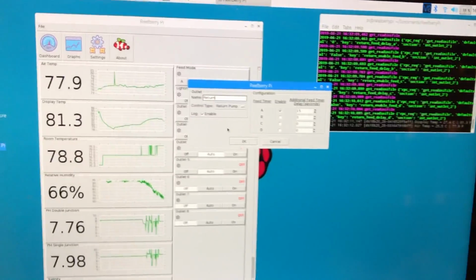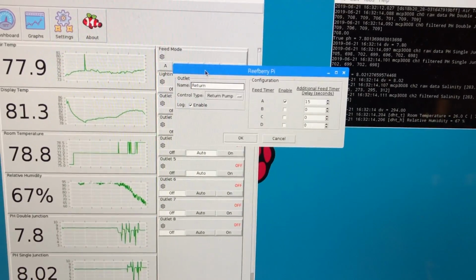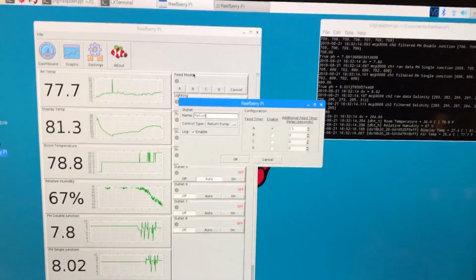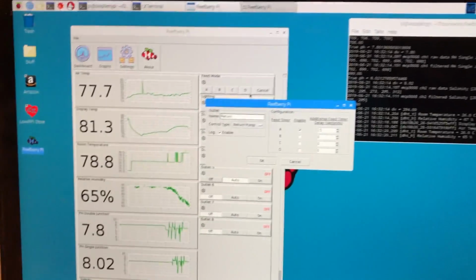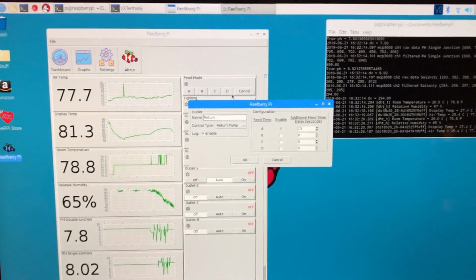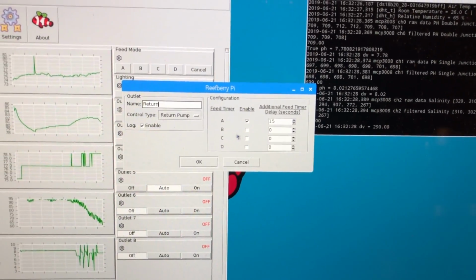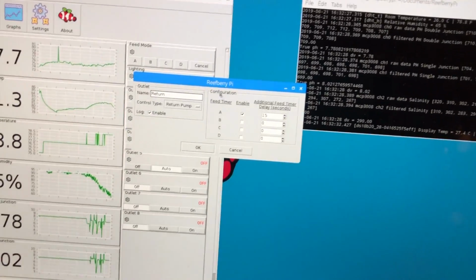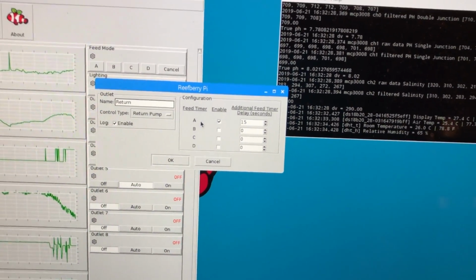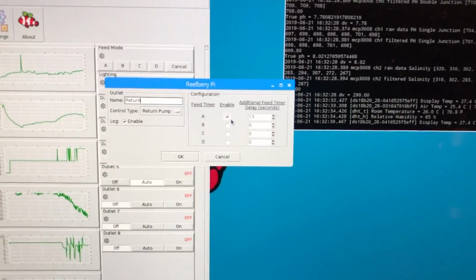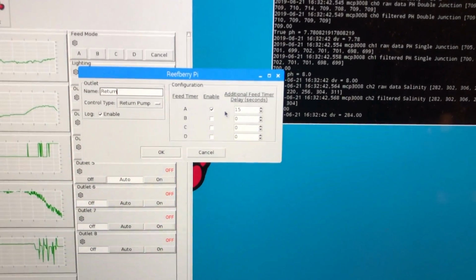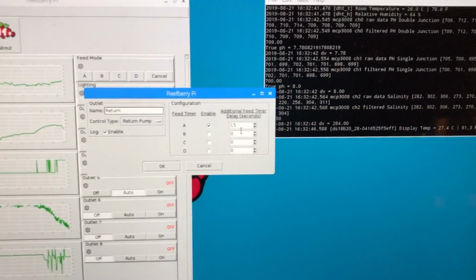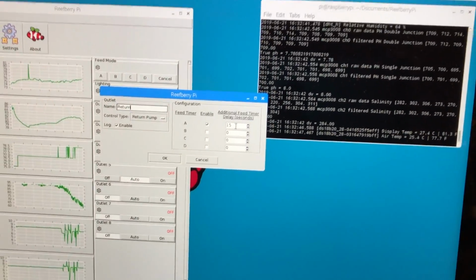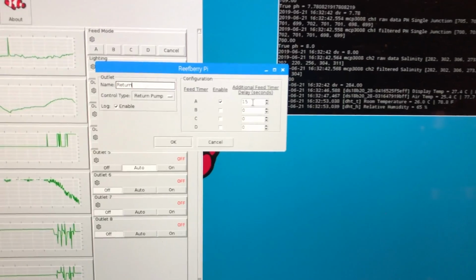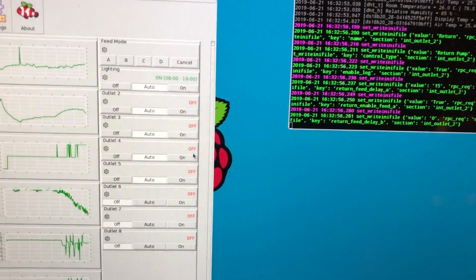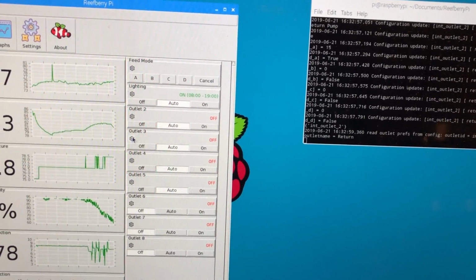Now here's where we'll get to make a couple of decisions. I failed to mention before, but there are some feed modes. So you could program up to 4 different feed modes and set that for as long as you would like. I think I have feed mode A set to 1 minute right now. So what'll happen is when I click on A, it'll start a 1 minute timer. And since I have the checkbox next to A, it's enabled for feed mode A. It'll turn this outlet off. And then when the feed mode has expired, it'll turn it back on, but it's going to give it an additional 15-second delay, which we'll see in just a moment. So let's say OK to that.